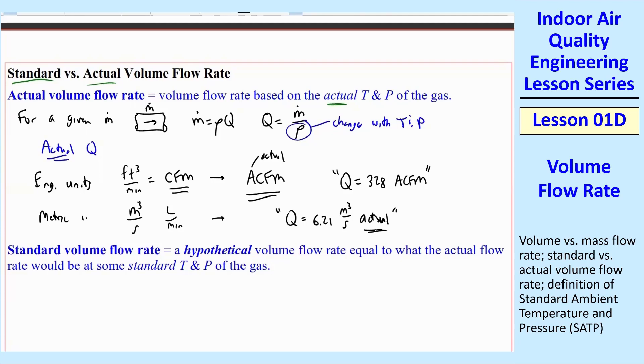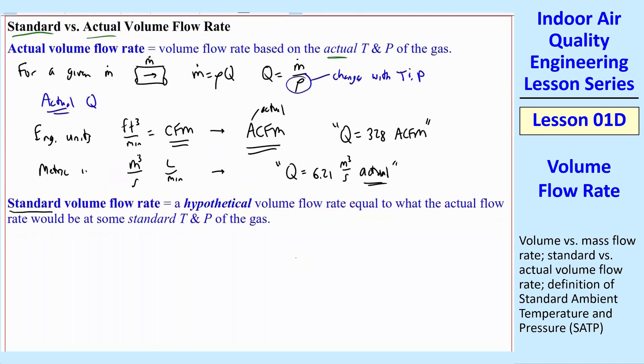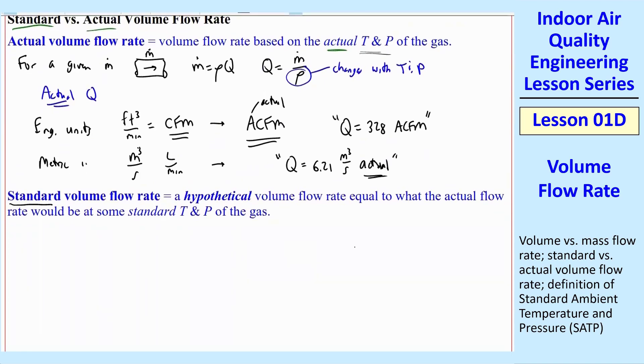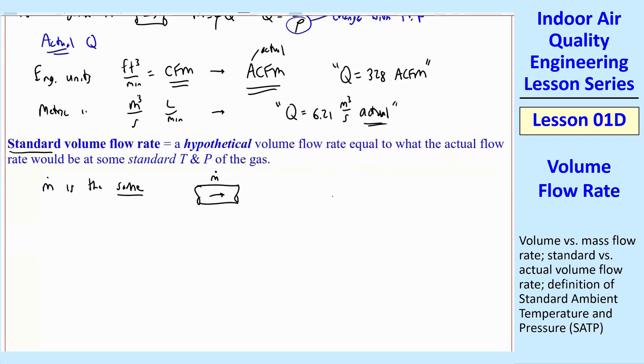In metric, it's not quite so simple. We typically use meter cube per second or liters per minute, etc. And there's no special unit. So we would have to write this as Q equals, say, 6.21 meter cube per second actual. You would write the word actual there to indicate that this is an actual volume flow rate. So all of that is typical of what you've done in fluid mechanics, so nothing new there. What may be different for you is this so-called standard volume flow rate. This is a hypothetical volume flow rate equal to what the actual flow rate would be at some standard temperature and pressure of the gas.